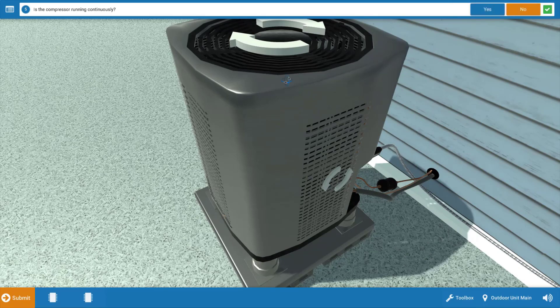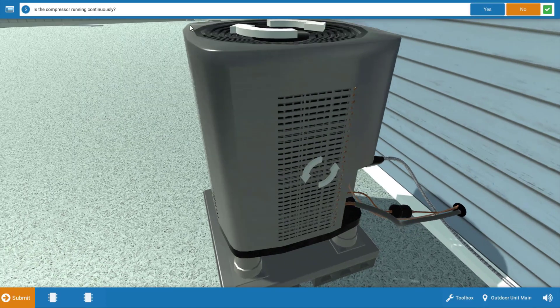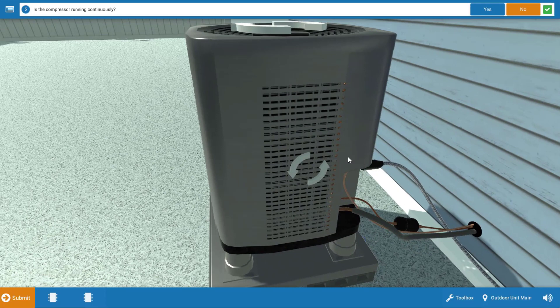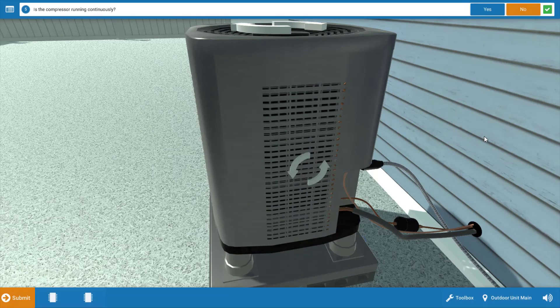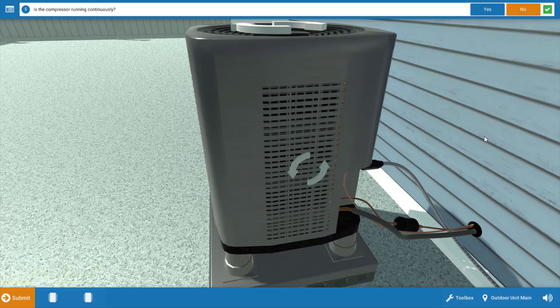Next, we need to check the compressor. Now, it appears the compressor is not running based on the graphic. You could always use a clamp on ammeter and clip it on the common wire of the compressor motor to see if there's any current draw for further verification if the compressor is running or cycling. So the compressor also is not running continuous, so we're going to click no on our procedure guide.